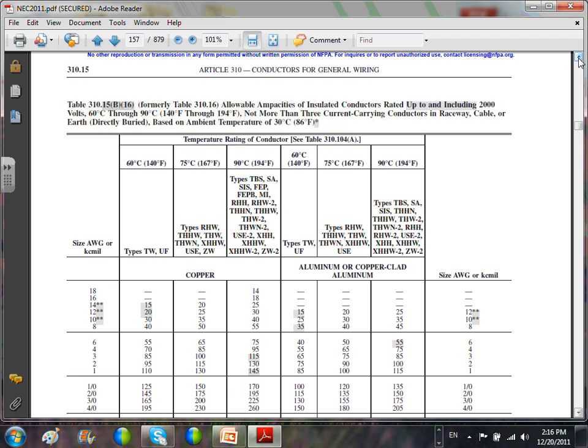The code says if it's continuous load, and the definition of continuous load, you have to run fully for 3 hours or more, fully, at full load. So if you have a motor that's running at half load, that's not continuous. It has to run fully.